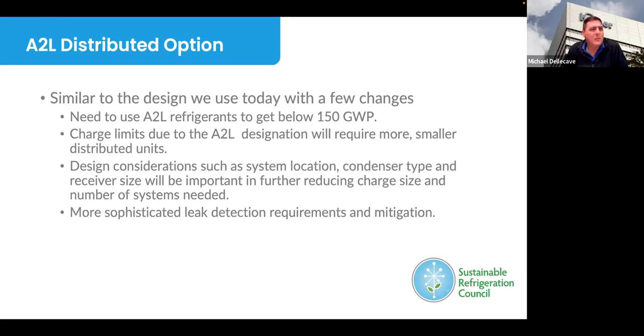One of the items that A2L brings to the table that's a little different than what we've done in the past - I know everybody's looking at leak detection, but leak detection is required with A2L, and it's required on a level that most of us don't have in our stores today, to not only detect the leaks but to mitigate them. So that's going to be a little bit new. It'll obviously be at cost, but it'll also have some benefits we can talk about here in a minute.